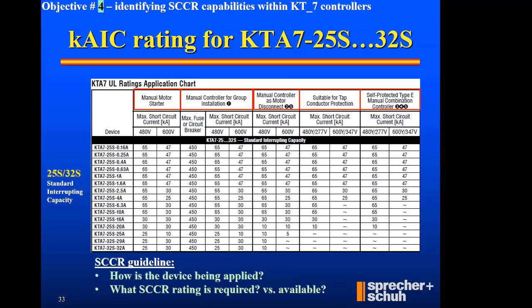Moving over one column to a manual controller for group installation. Now I've got group installation rules in that, looking down the 480 volt column, yeah, I can get 65 KAIC all the way down to the 10 amp model. Now I still have ratings for the 16 through 32 amp. Yeah, for group installation, as long as there's upstream protection, I'm still getting KAIC approval on this product alone.